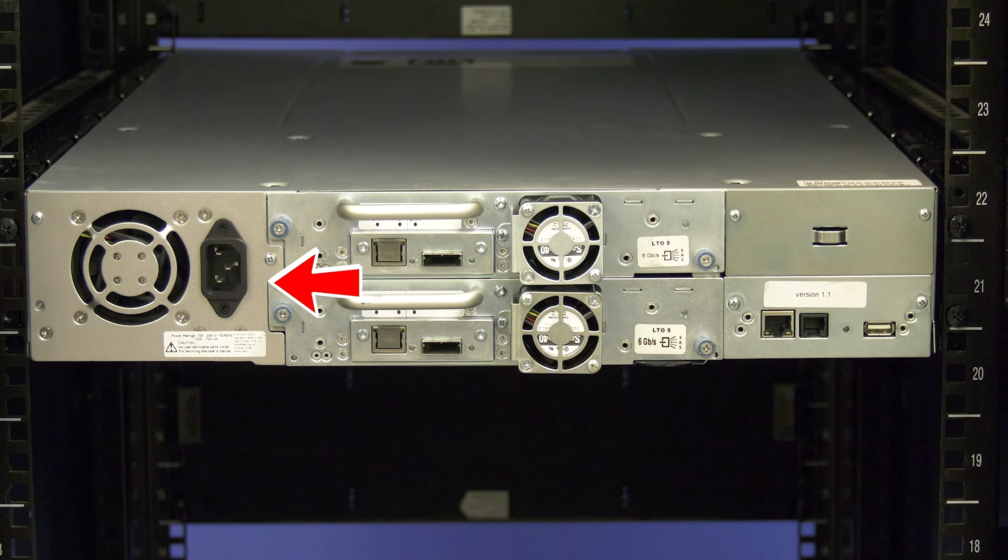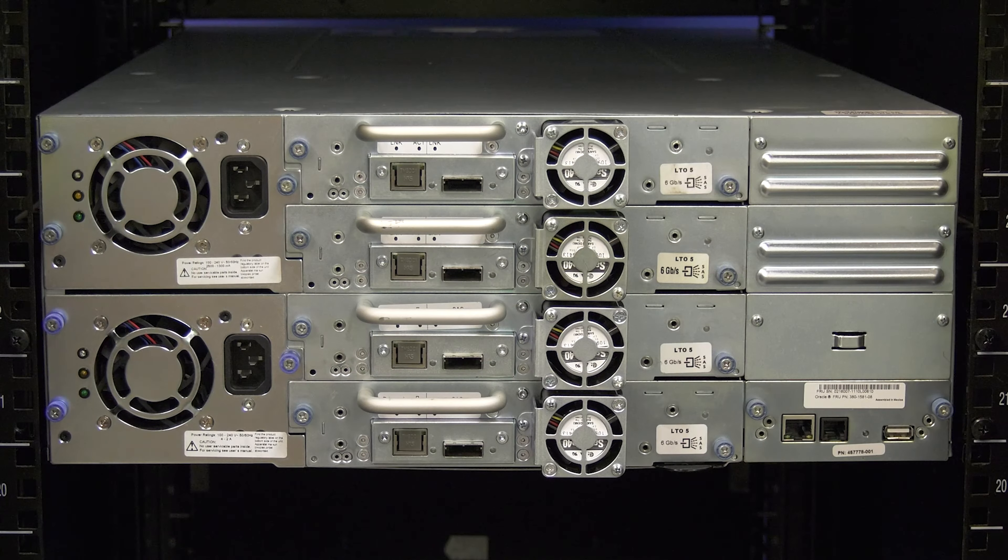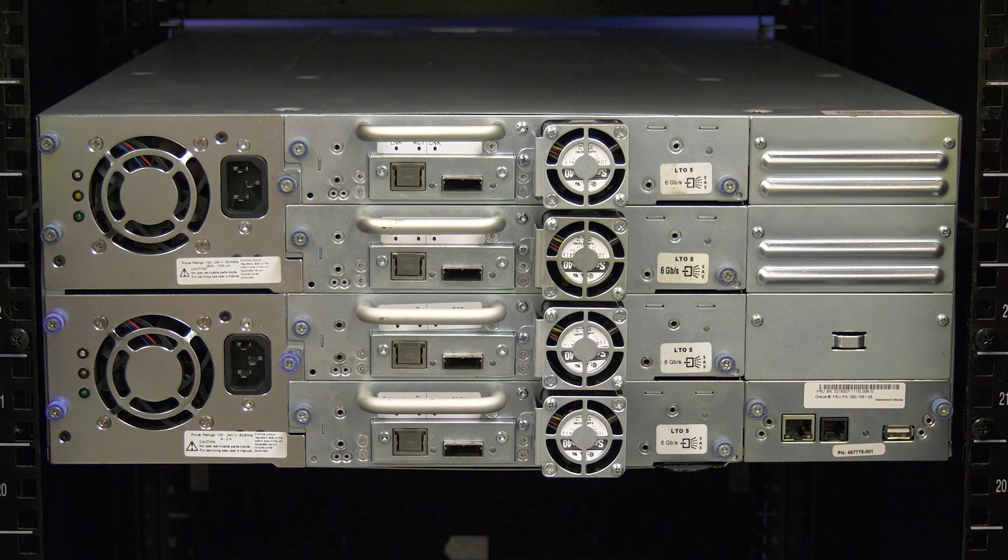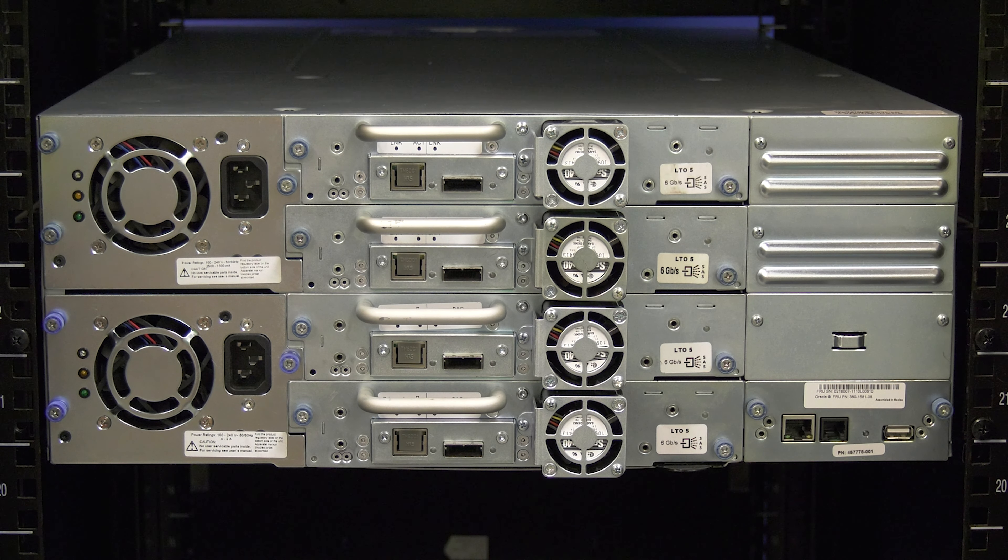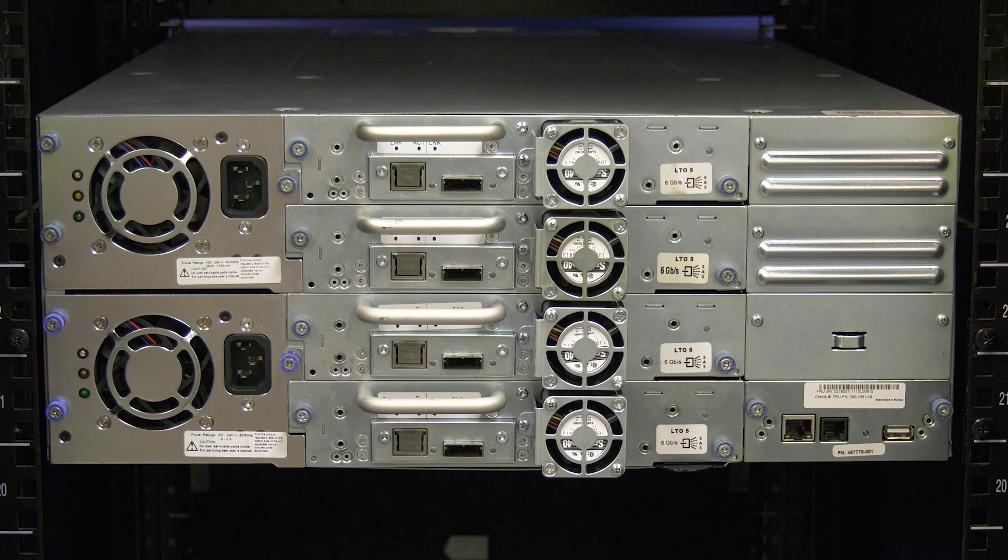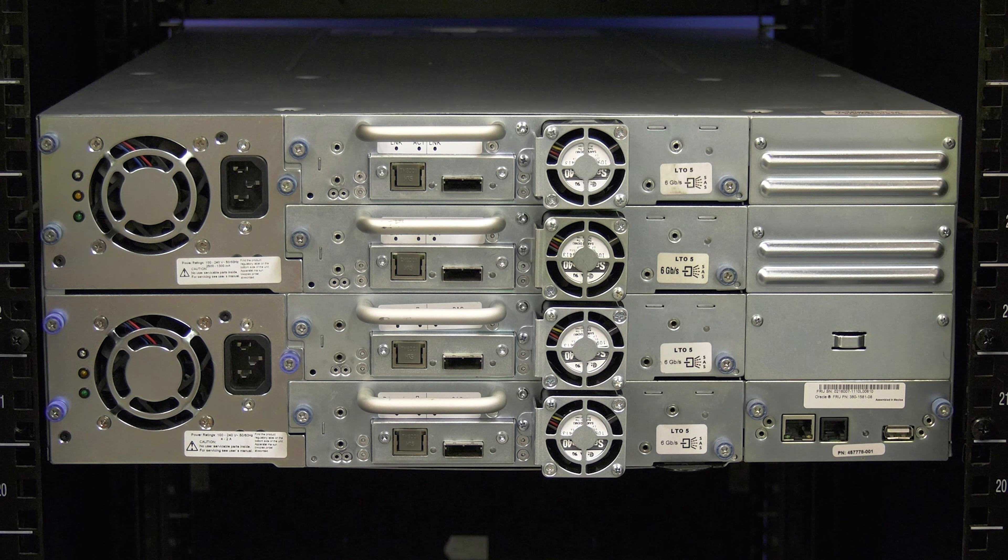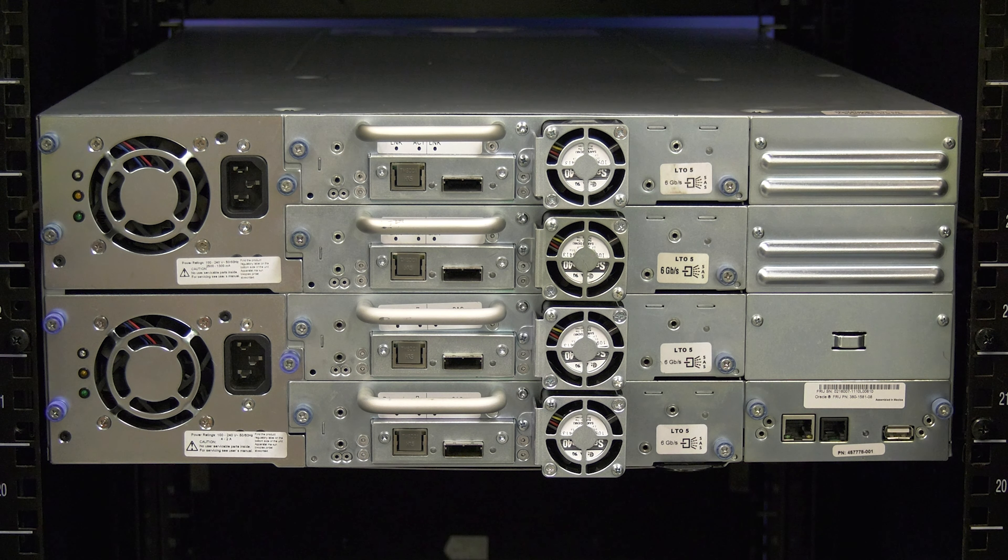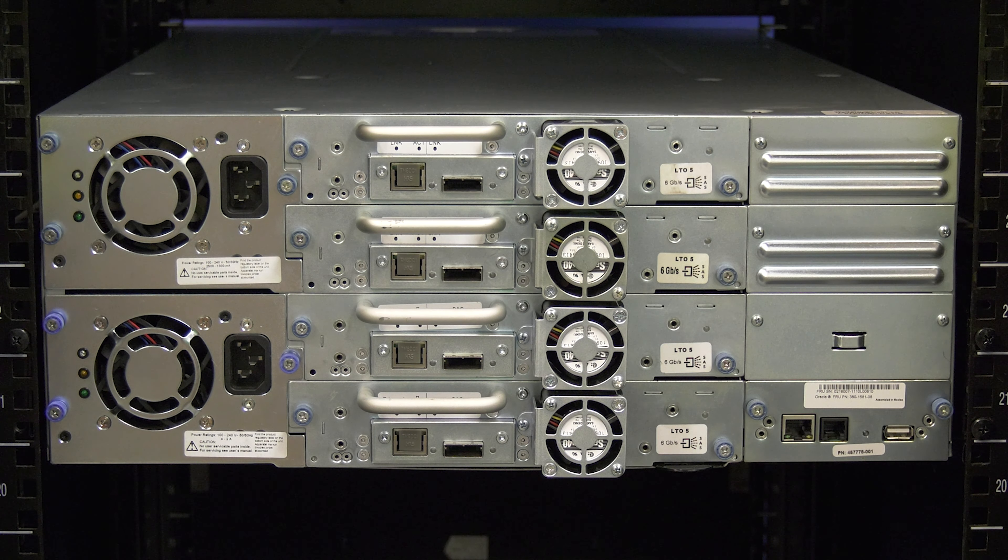If this is the 200S, there will only be a single power supply in the rear of the machine. If it is a 400S, you may have redundant power supplies installed. If this is the case, you will need to determine which supply is faulted so that you can replace the proper one.